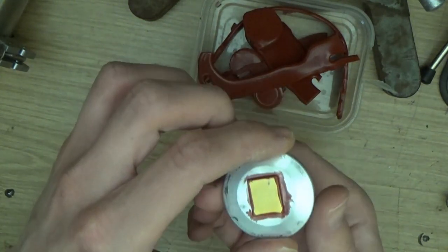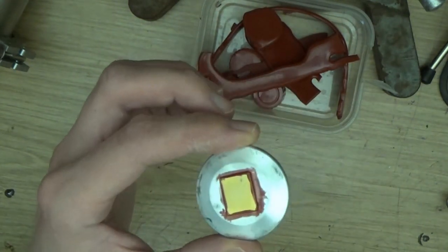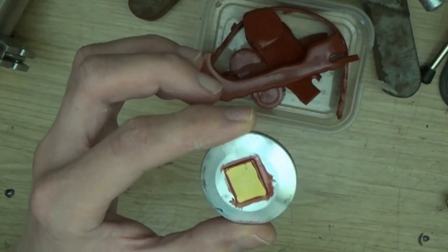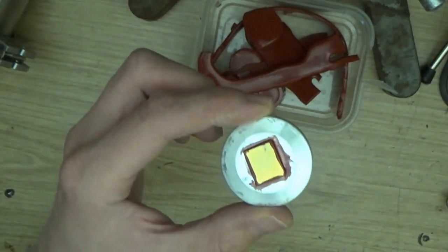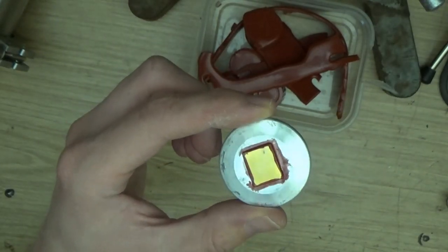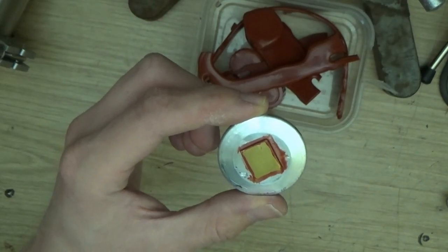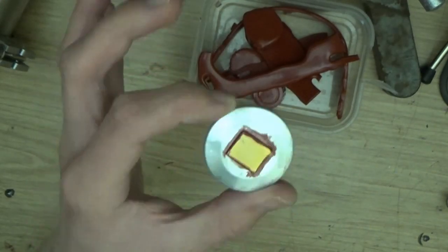And this pumped down so well that you would think the wax wasn't there. I got down to 10 to the minus 7th millibar or torr approximately, which is the best I have ever gotten. And that's as good as it gets within a reasonable timeframe, unless you heat it or leave it overnight. So I'm very, very happy with that.